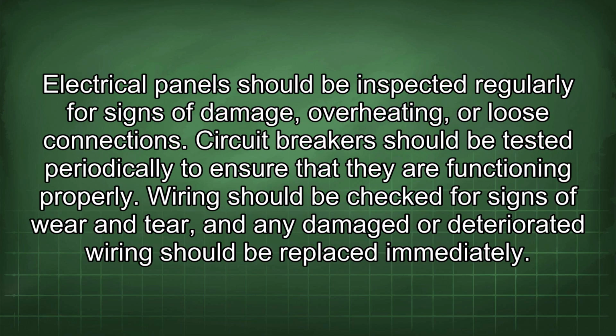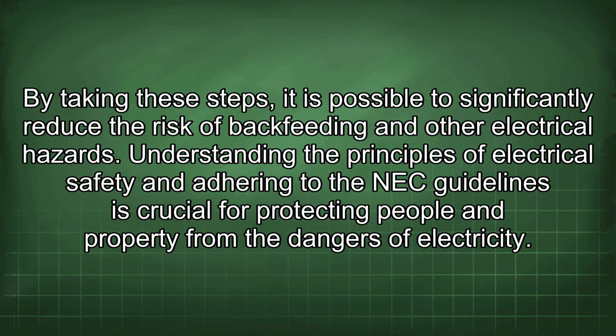Electrical panels should be inspected regularly for signs of damage, overheating, or loose connections. Circuit breakers should be tested periodically to ensure that they are functioning properly. Wiring should be checked for signs of wear and tear, and any damaged or deteriorated wiring should be replaced immediately. By taking these steps, it is possible to significantly reduce the risk of backfeeding and other electrical hazards.